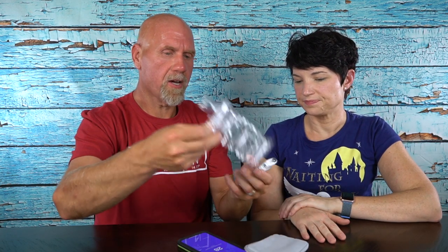What is different about this one is that it actually goes through a complete calibration process. It tells me right here that it's going to start doing it. If you look on here, it's got a countdown. What it's doing right now is initializing the sensor to eliminate all of the stuff that may be floating around in the air. Yeah, the environmental things that it needs to burn off. And it does come with a bunch of these little mouthpieces as well. Now, still, you don't want to store this in your kitchen.